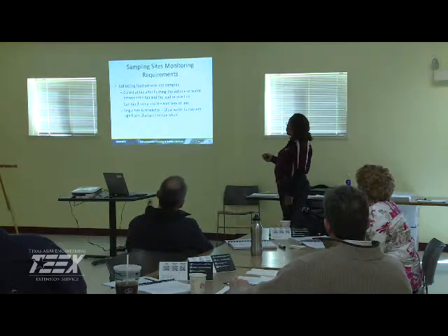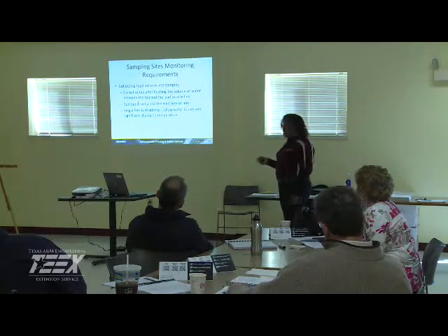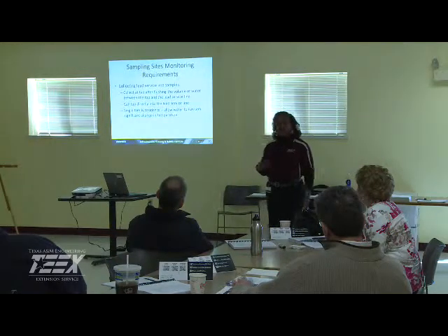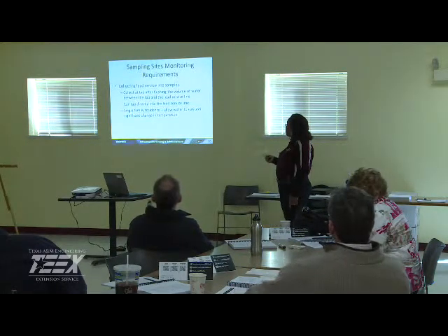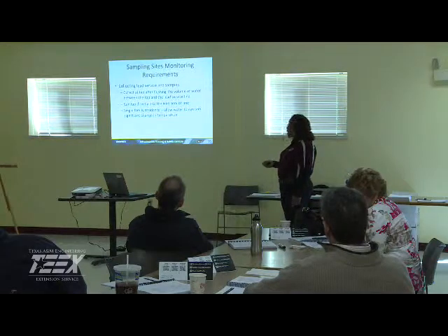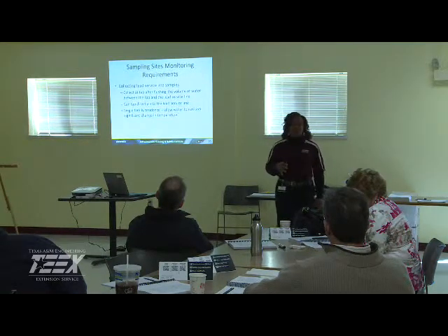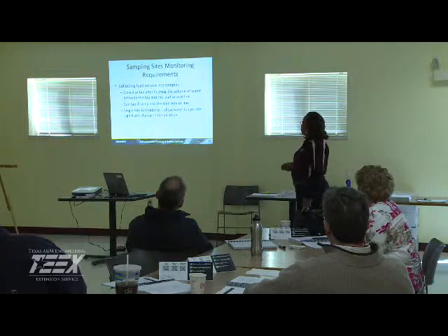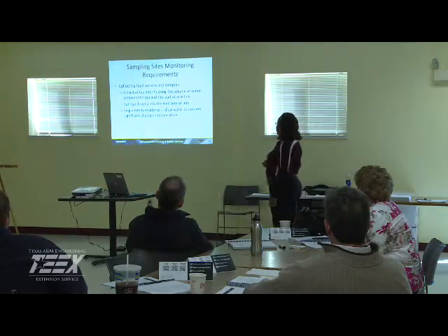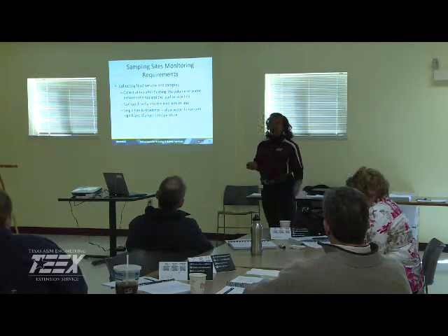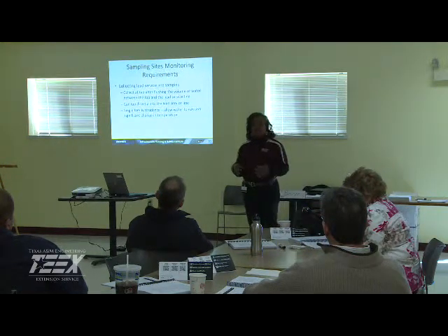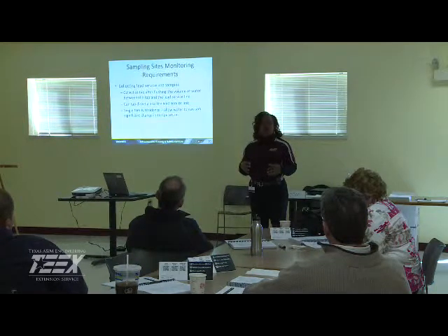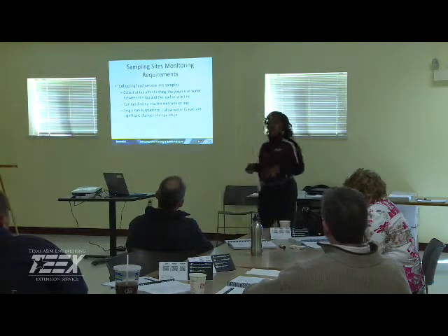All right. Now, if you're collecting samples from the lead service line, we want to make sure flushing takes place. So collect at a tap after flushing the volume of water between the tap and the lead service line. You can tap directly into that lead service line to pull your sample. And if you're dealing with single-family residents, again, you're going to instruct them to allow the water to run until there is a change in temperature prior to collecting that sample, so we can make sure we have a representative sample. Okay.